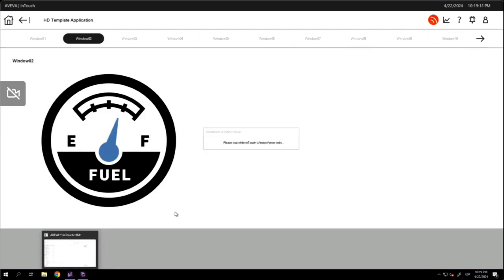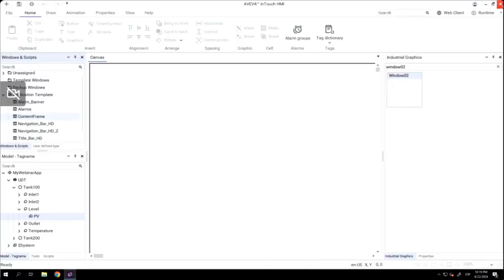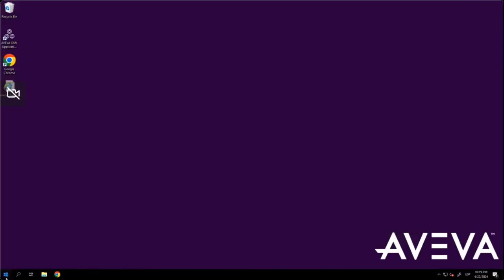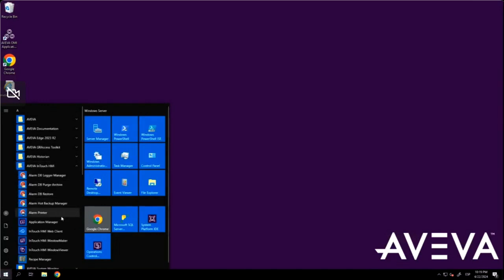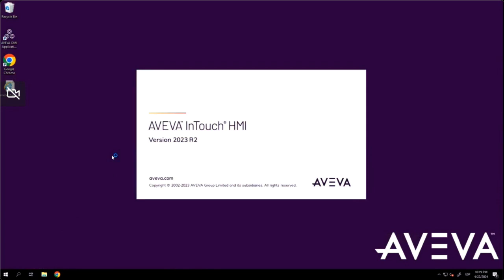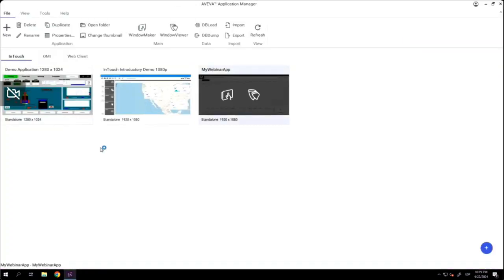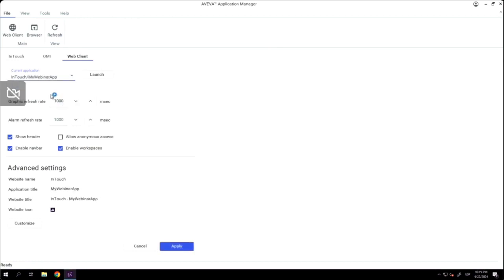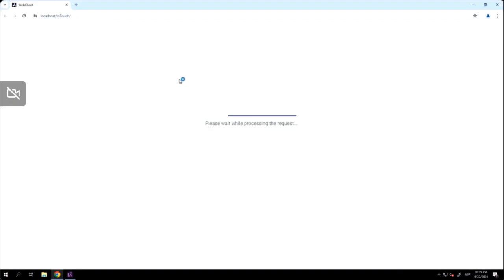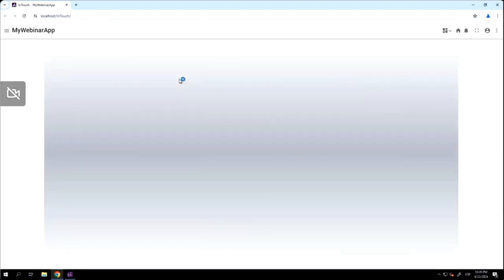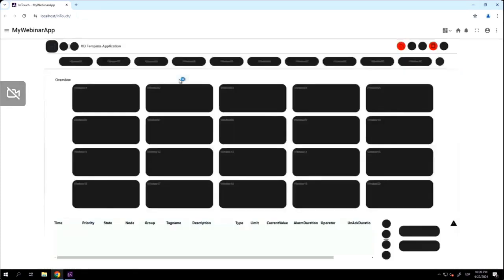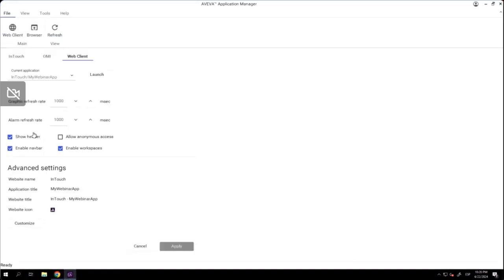Now, it's time to run the same application using InTouch Web. The first thing that I need to do is close everything. I need to open again InTouch Application Manager. And I will go to the last tab that is Web Client. I will select from this list the applications that I want. This is the one that I want to execute in the web server. And now I can run the application in this web server. I will launch the application. The web browser will appear. Now, it's loading the application.